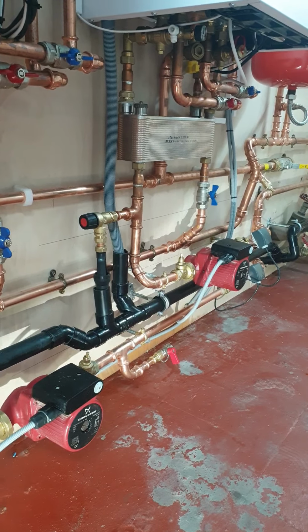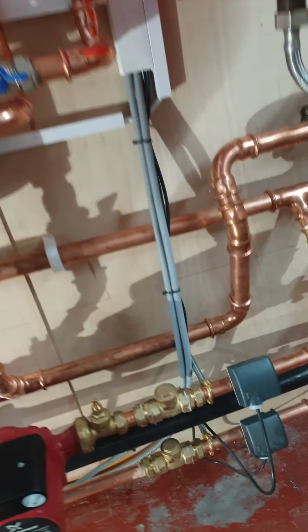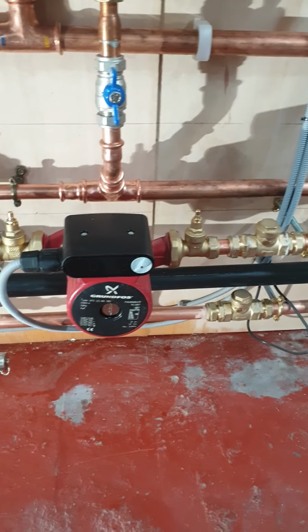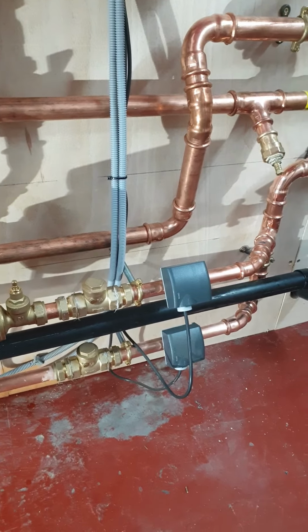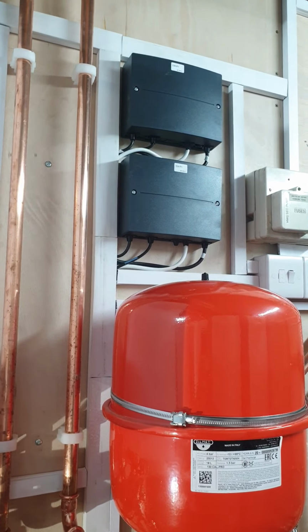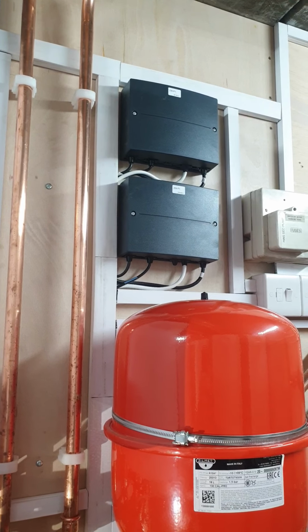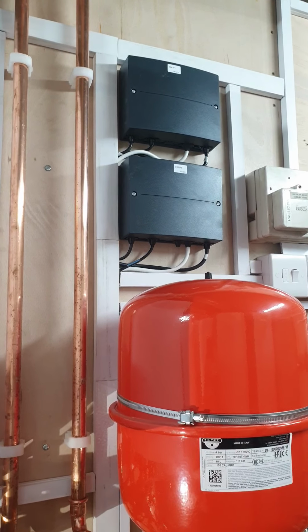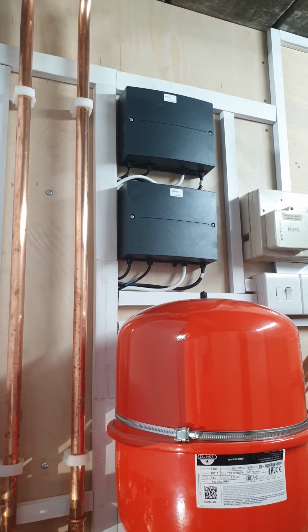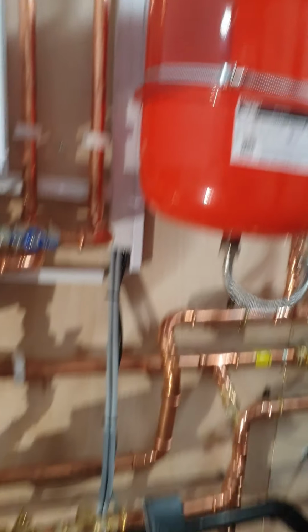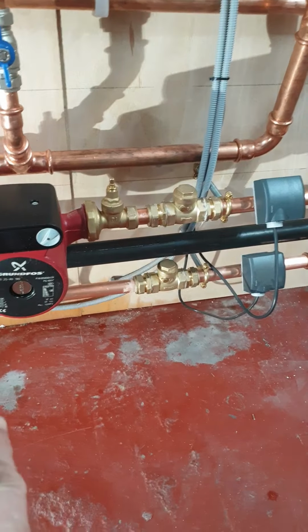This nice new conduit that I picked up for the pumps, just to go on the wires. I quite like this little feature. Sensors there, so we've got the low loss header sensors. These are run from the EMP1 relay boxes. So each boiler has got one of these relay boxes, and for some reason Viessmann require one of these to allow us to connect in the pump and the secondary flow sensors, or low loss header sensors, as they would be if this was low loss headers.